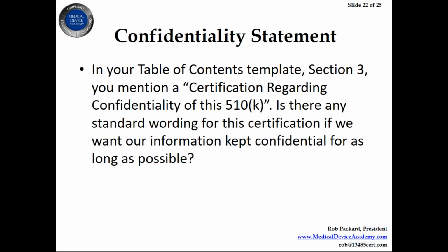In general, that's not a good idea, because what if your 510K is rejected? So everybody wants to talk about their new product as early as they can, but you fill out the certification of confidentiality for a reason, and part of this certification states that you're not going to tell people all about your product before you get a 510K. And if you do, you're supposed to notify the FDA and let them know that you've already presented this at a trade show, but you've said it's 510K pending. So there is language around that confidentiality statement.